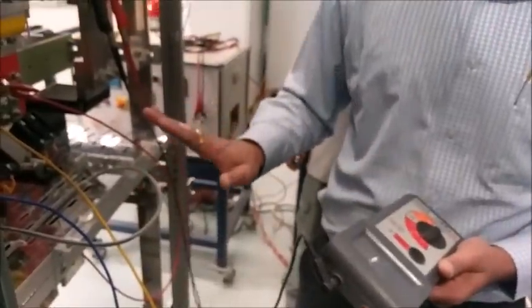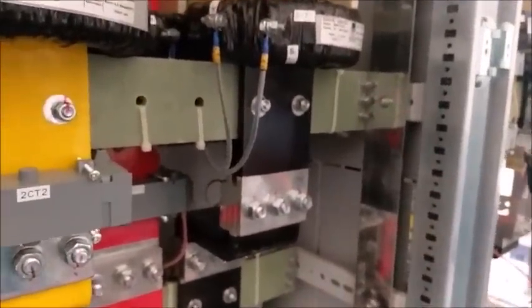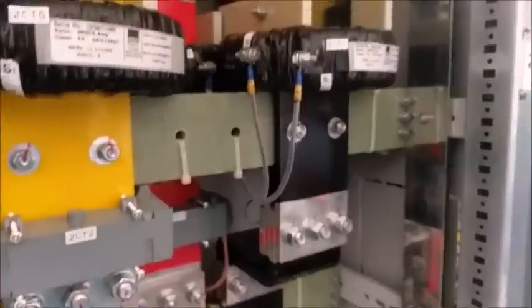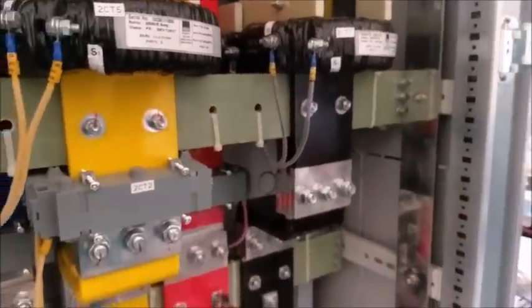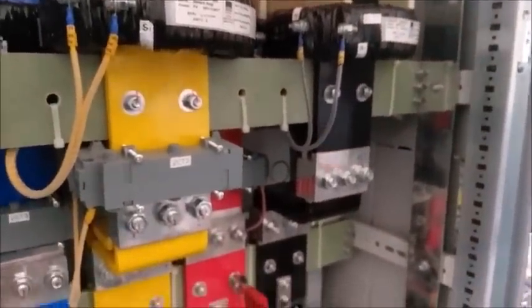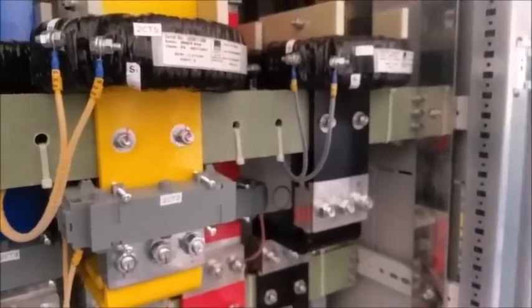You can short it. Suppose up to this level is okay, then I can check from here to here. Like that also I can pinpoint where the problem is. There should not be continuity here. And if you need to check from here to here, just check if there is continuity between them or not. If there is continuity, something is wrong here, a failure.